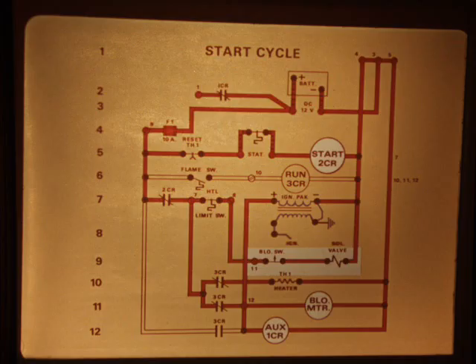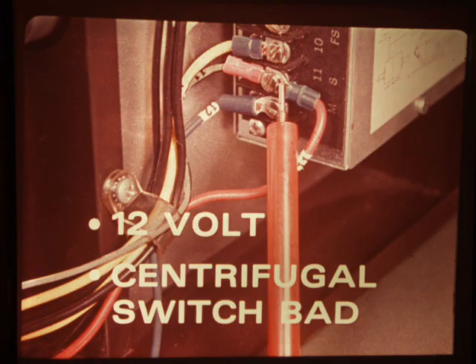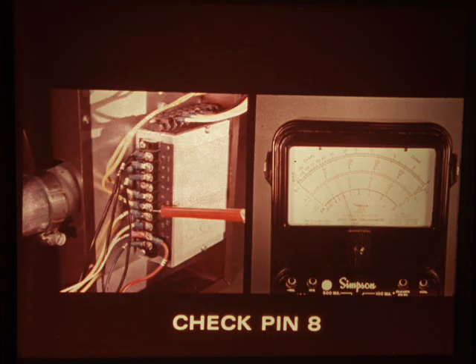Now, remember that the solenoid gas valve is fed from the centrifugal switch on the blower, and that feed is from pin 11 on the control box. So measure the voltage at pin 11. If you get 12 volts at pin 11, but can't get voltage to the gas valve, the centrifugal switch is bad. You then have to replace the blower assembly.